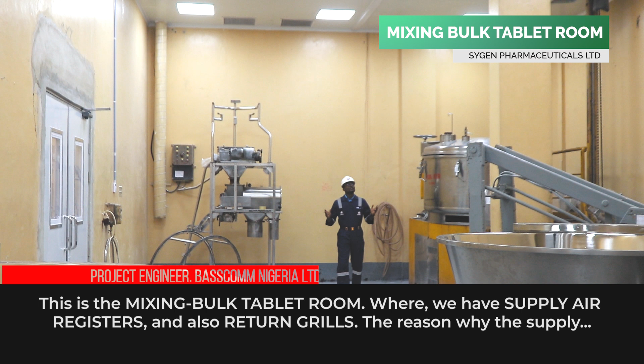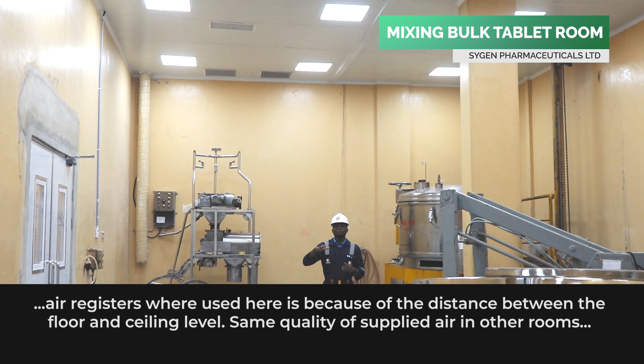This is the mixing bulk tablet room. Here we have supply registers and also a return grill. The reason why the supply registers were used there is because of the distance between the floor and ceiling level. The same quality of supplied air as in other rooms, with a distance from the ceiling to the floor of 3 meters, has been achieved. The same in this particular room has been achieved, nothing changing. Same design, same quality, same HVAC ISO Class 8.